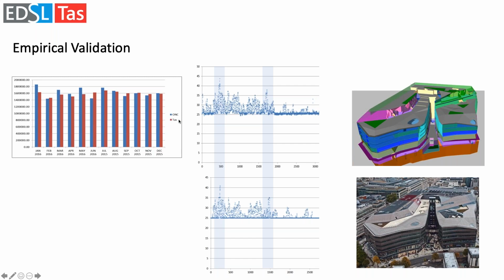The good thing was that when we got down to some things that should respond pretty closely, not just at the monthly or annual level but at the hourly level, this is a sensor on one particular pipe in the mechanical room. And this is the same pipe in our HVAC schematic reported for the same period from the summer through to the winter. And you can see the shapes very closely matched. Ours is obviously a bit tidier than the actual sensor, which is a lot more real and messier.